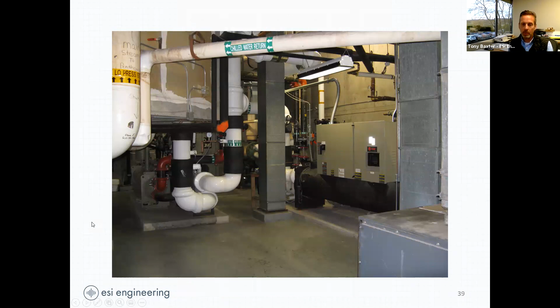They were put in, in my opinion, without any vibration isolation. Here's a very, very, very thin little rubber waffle pad that was pretty much compressed completely. That was the isolation that was put in there. These were Trane chillers, and they were not designed to have isolation, like spring isolation or air isolation or any other type of isolation. Trane said these had to be on pads on the concrete. They were relying on this concrete to give them support for the equipment, the lateral support, and you couldn't put a spring under here. These plates weren't really designed to take those loads.